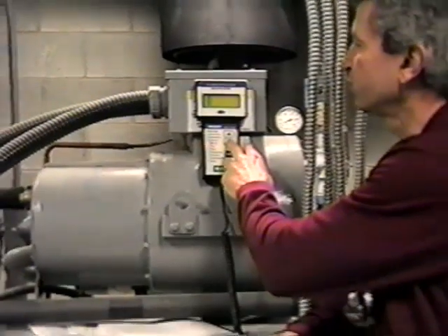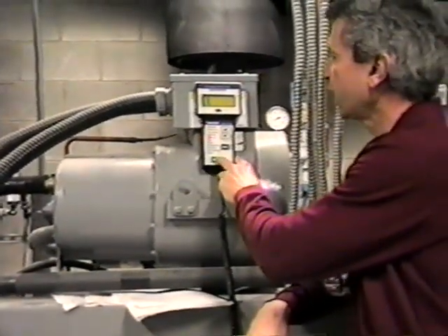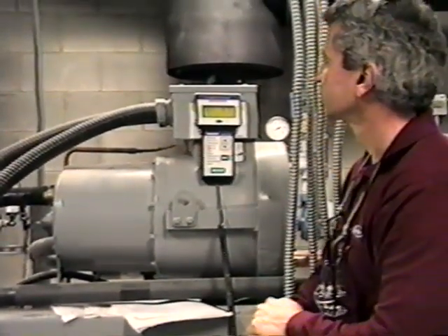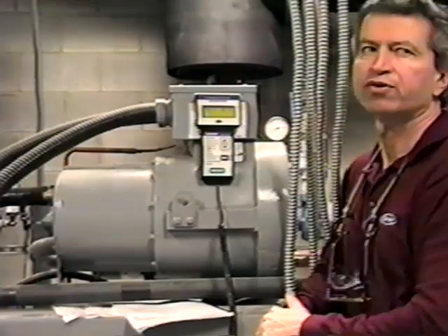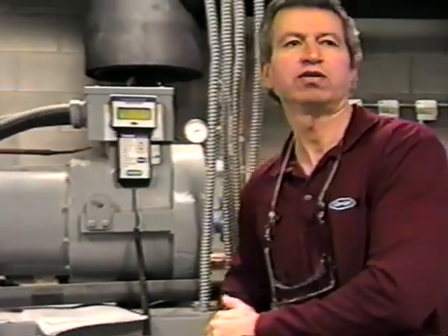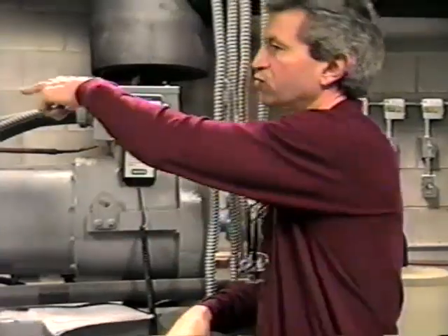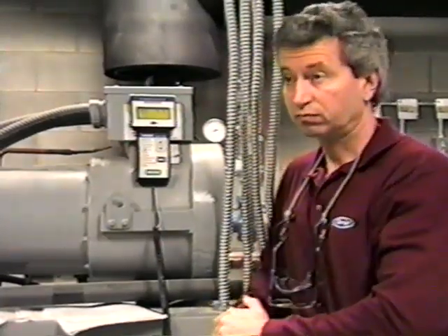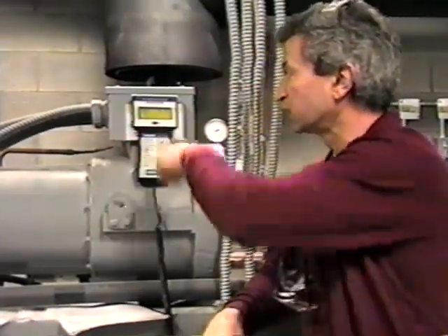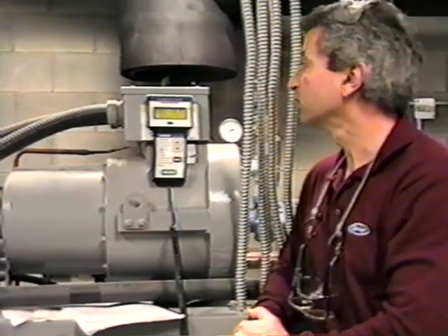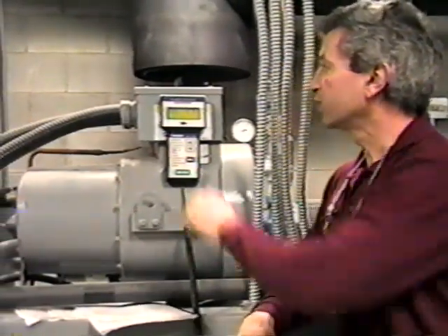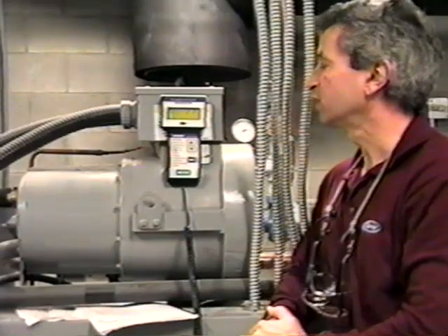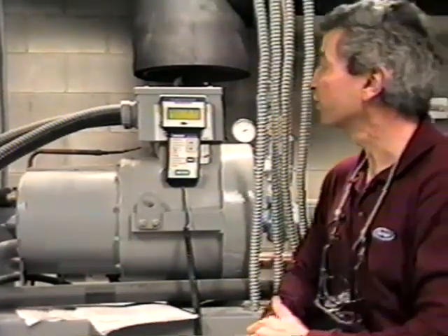Heat, again, it's not being used for heat. Head, I think we are using head pressure control here. I believe we're sending a signal to the drive for the tower fan. So that set point is significant in this case. We're controlling head pressure, and again you can have a set point different on one or the other circuit, but both are set for a 90-degree set point at this time.